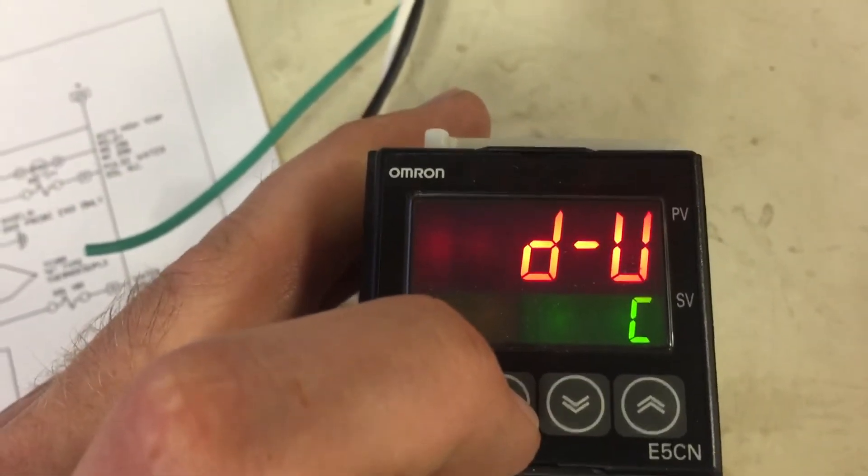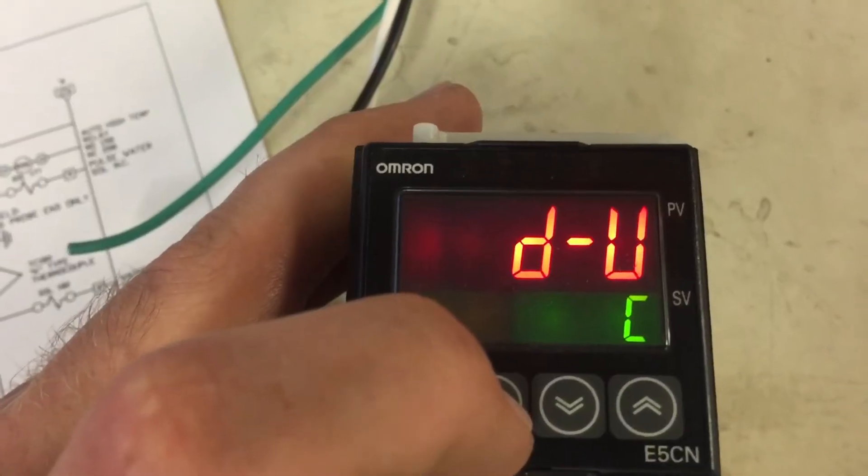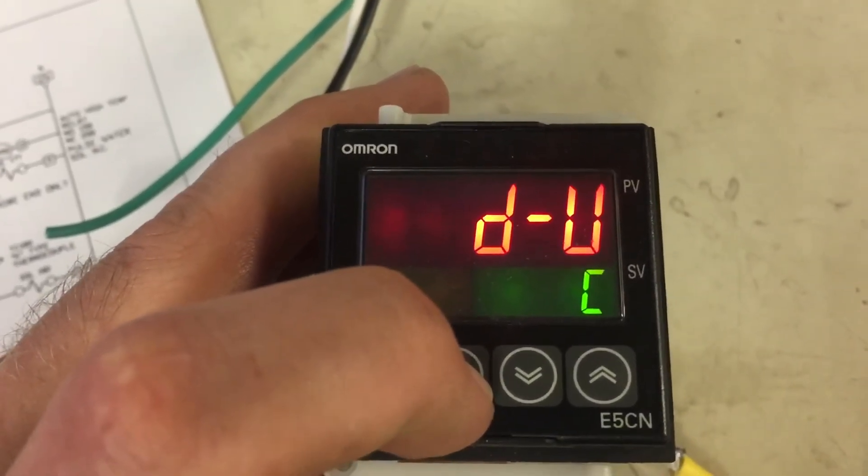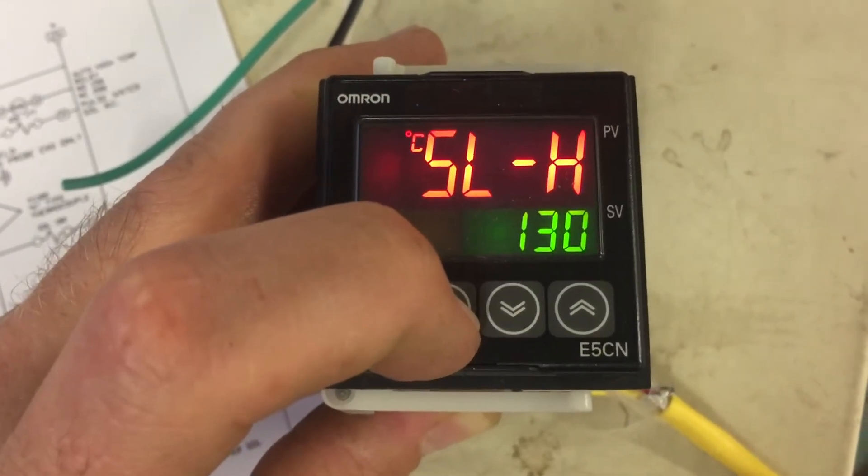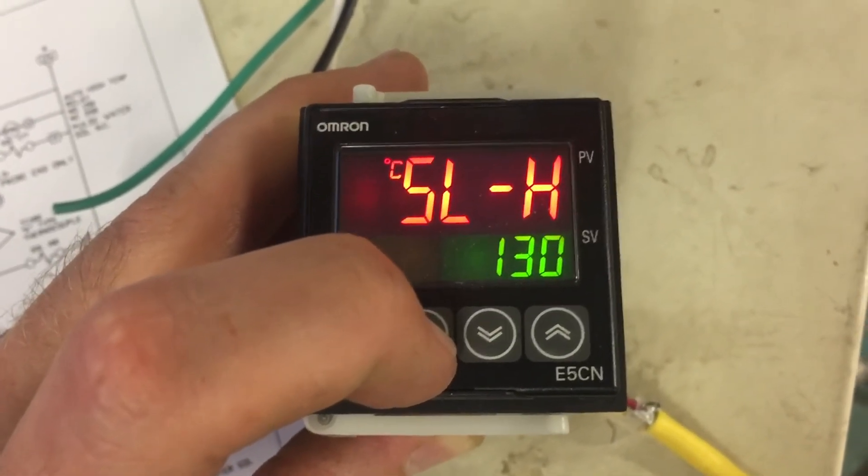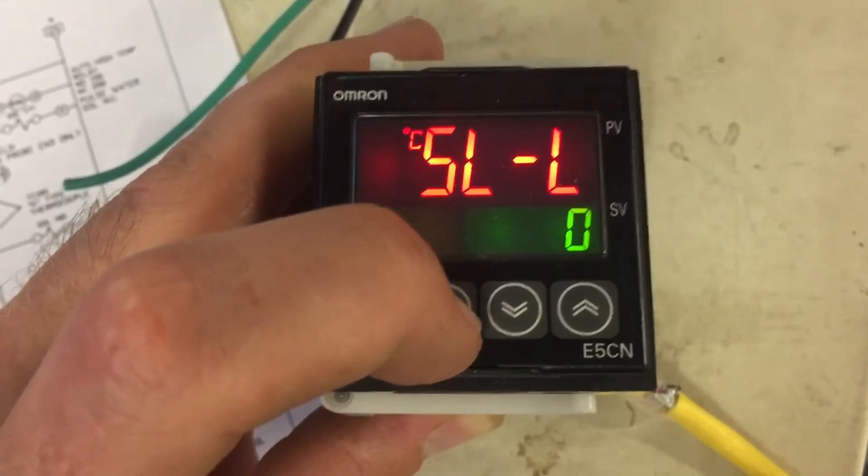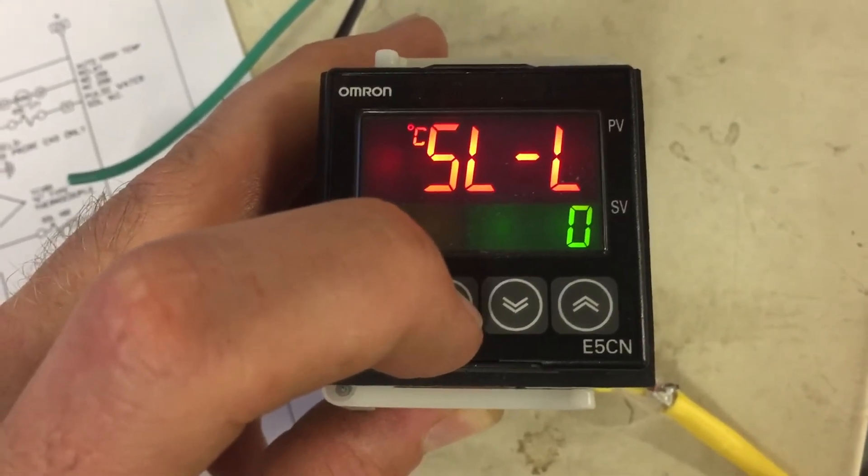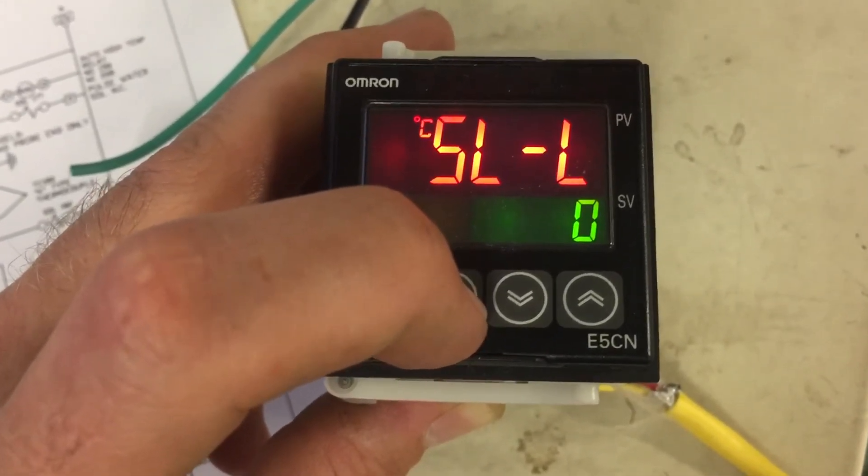This is the unit type. What it is, is Celsius normally for Canadian units and Fahrenheit for United States and Mexico. The set limit high for Celsius is 130. Set limit low. On demonstration purposes, I've set this at 0, but normally it's set at 100 so that the operator doesn't flood the unit.